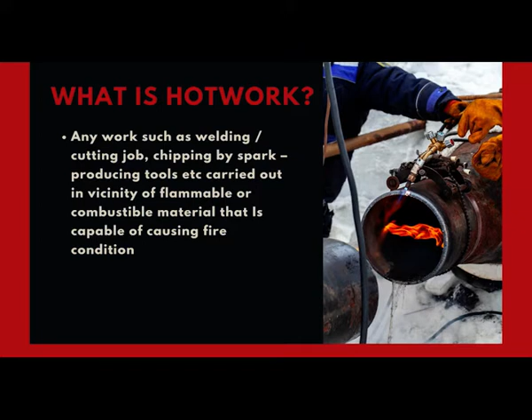For a hot work permit, the equipment or area should be tested to determine the explosive range using an explosive meter by taking air samples. Cleaning or ventilating can clear explosive content. For example, if a process vessel has a leak that needs to be fixed by welding, the operating crew must ensure the vessel is completely drained of hydrocarbon liquid, water washed, opened up, and all hydrocarbon vapors vented out using steam or inert gas, then confirm no hydrocarbon vapors remain using an explosive meter. Only when satisfactory results are obtained can the work permit be given.